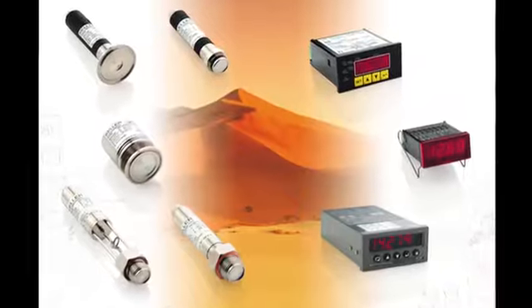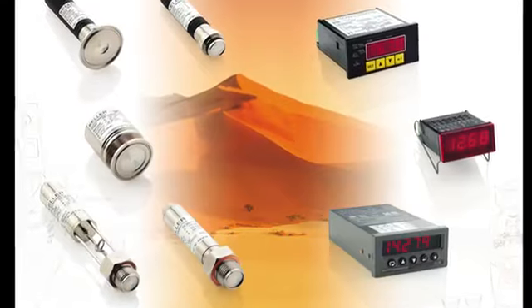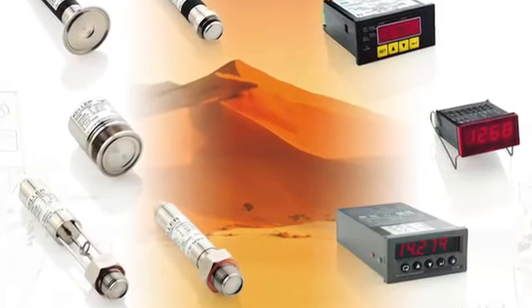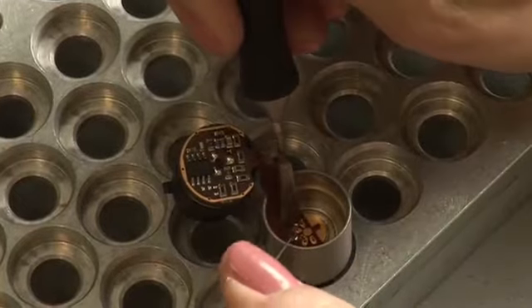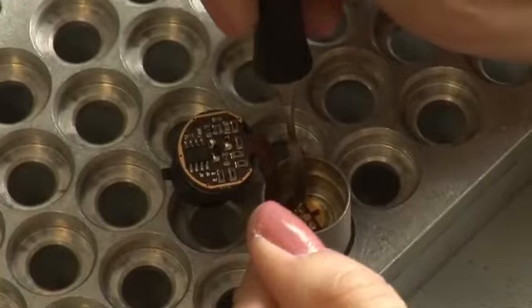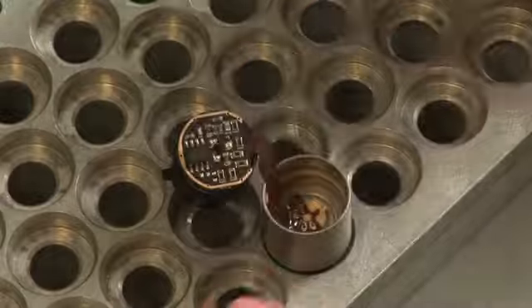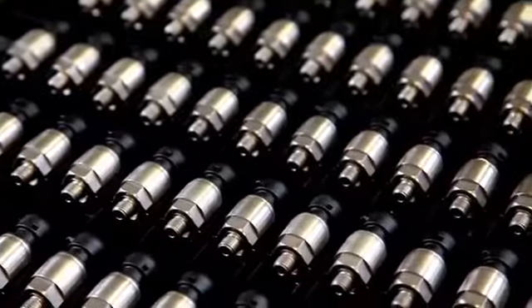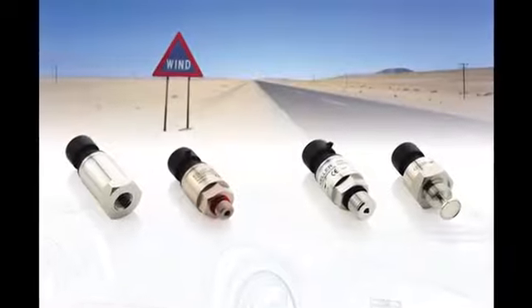Pressure transmitters are another key product sector for KELLER. These transmit electronically compensated standard measurement signals. In other words, a pressure transmitter is an enhanced type of pressure transducer, which allows the user to carry out highly precise measurements with little technical outlay.